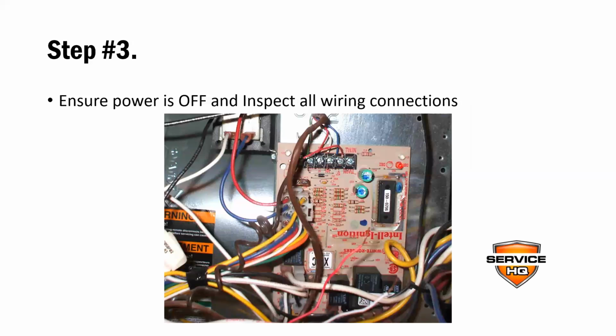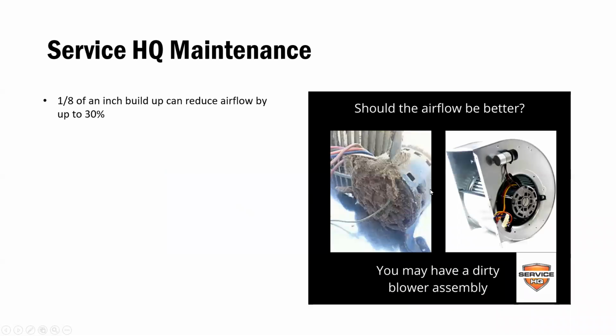So step number 3, we're going to make sure that the power is off to our furnace, and we're going to inspect all the wiring connections. Now, if we come out, we're going to actually tighten all these terminals and make sure these Molex plugs are good, make sure all the spade terminals are good. And then we also are going to check the blower wheel, the blower assembly, because like I said earlier, this one right here, this is a dirty, nasty, disgusting blower assembly.